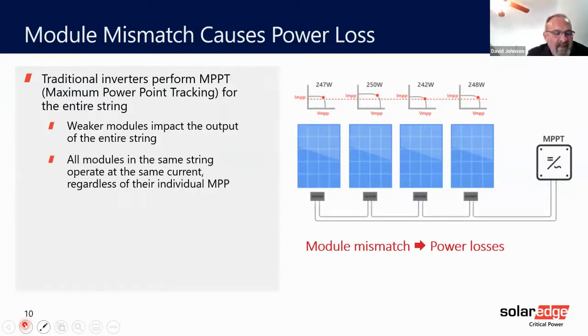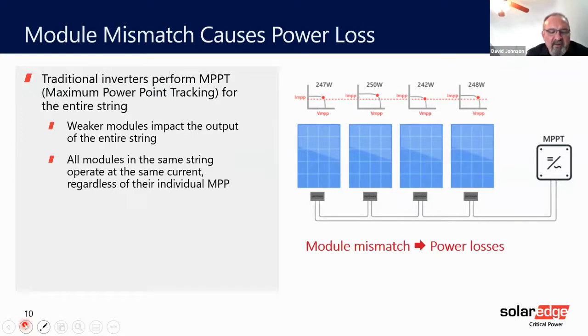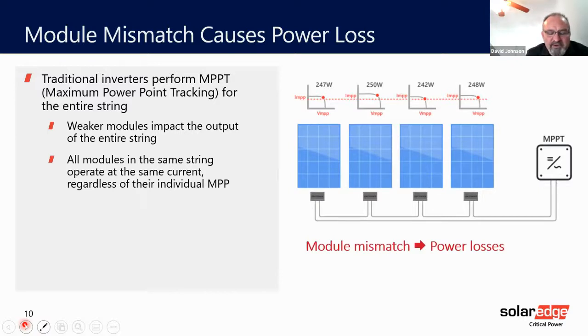Why? Each module has its own optimal working point, as you can see in the illustration here. If you only remember one thing from today's presentation, remember that module mismatch means you're losing money. Since the modules are connected in series, the weakest module will drag all of the others down — they will have to produce power according to its working point, which is lower than theirs.